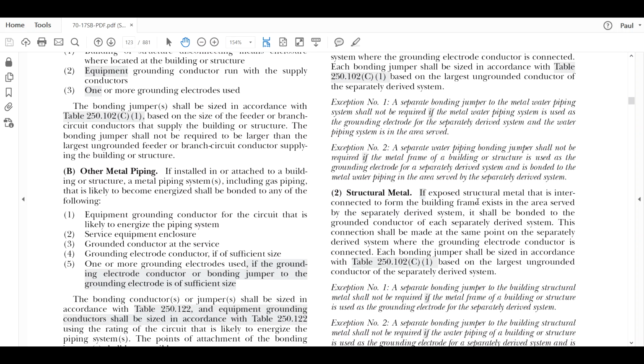If it exists in the area served by the separately derived system, it shall be bonded to the grounded conductor of each separately derived system. This connection shall be made at the same point on the separately derived system where the grounding electrode conductor is connected, and we already discussed that. It's no different than where it was for the water pipe ground. It's also sized the exact same way, so obviously this would be a 2 gauge for the structural metal as well. And again, if you had multiple separately derived systems, then each one of them would have to make a connection over to that structural metal.